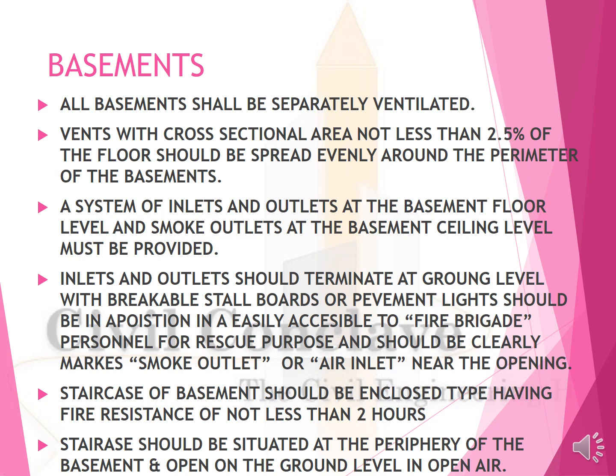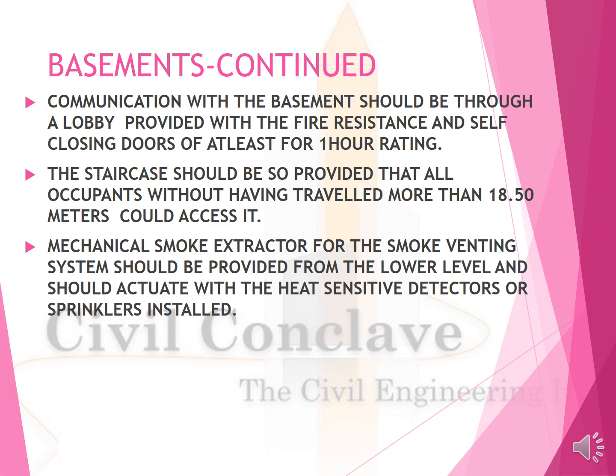Staircase of basement should be enclosed with fire resistance doors of not less than 2 hours. Stairs should be situated at the periphery of the basement, open on the ground level in open air. Communication with the basement should be through a lobby provided with fire resistance and self-closing doors. The staircase should be provided so that all occupants could access it without having travelled more than 18.5 meters.